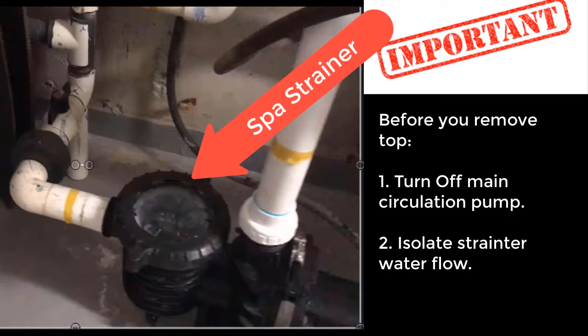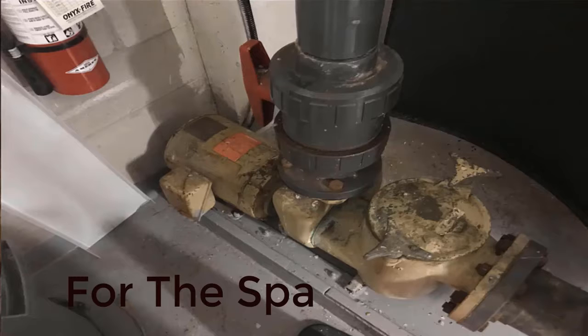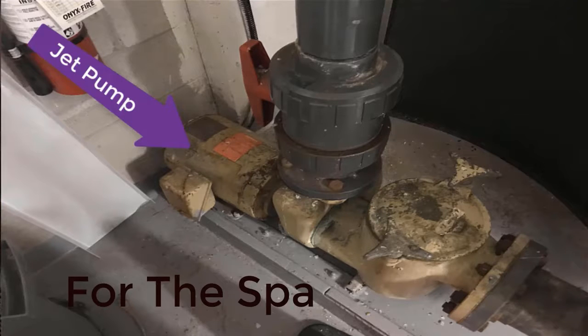Before you remove the screw off top of this, you have to ensure the circulation pump is off and the valves that provide water flow to the strainer are turned off. Then you can take the basket out and remove any debris stuck in it. Beside that, on the left, is the jet pump, the larger pump.